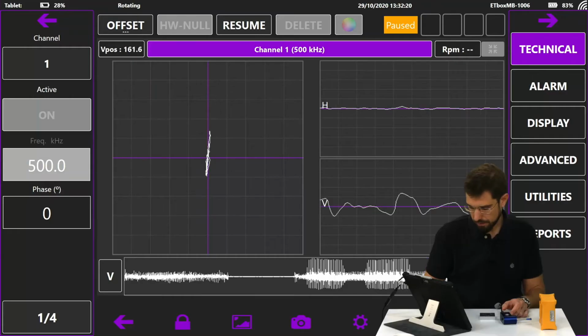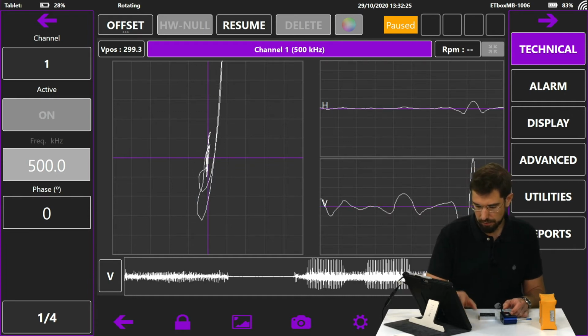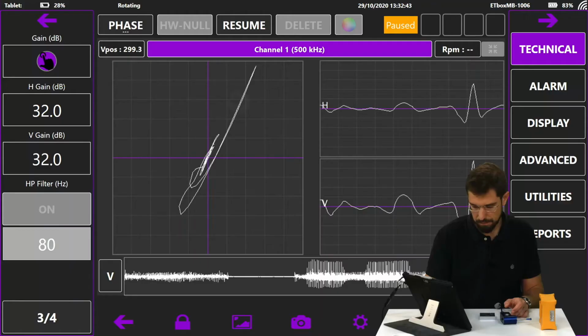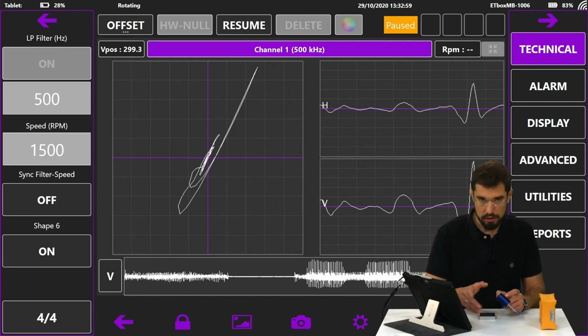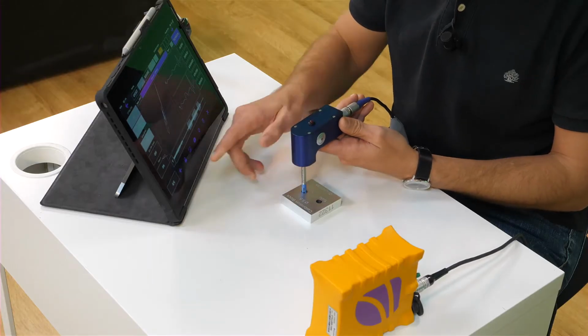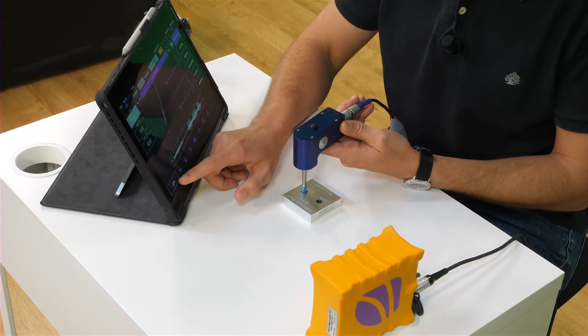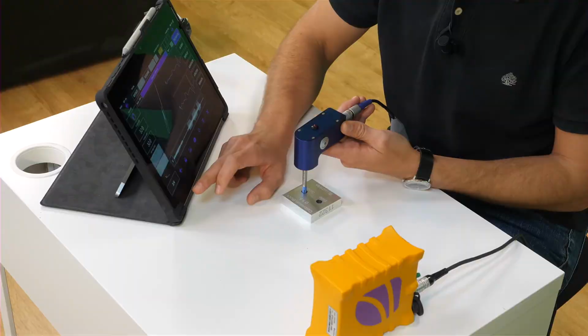This way, we can see the notch. We're going to do a calibration of the phase. There. And, well, the gain, in this case, is correct, so we're not going to manipulate it. Once we have the calibrated signal, I want to mention some of the configurations that we must take into account with this kind of probe, which are the activation of the filters, high pass and low pass.